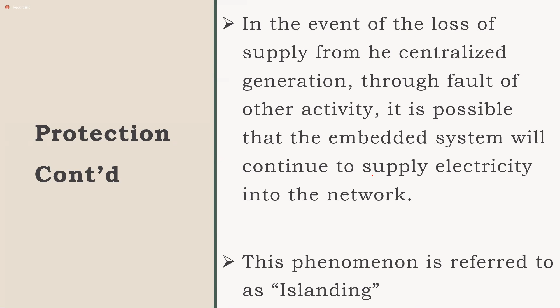So even though you have the disconnection, which may be deliberate on the part of the utility company for maintenance purposes, if there isn't also automatic disconnection or isolation on the part of the embedded generation, which will quickly isolate it from the grid, you may cause damage or injury to personnel. That's another consideration when we're talking about renewables and the integration of renewables.